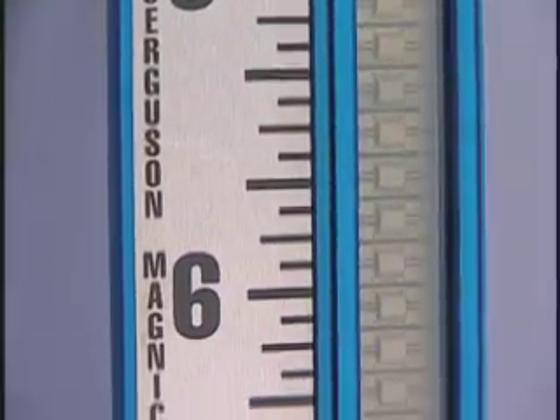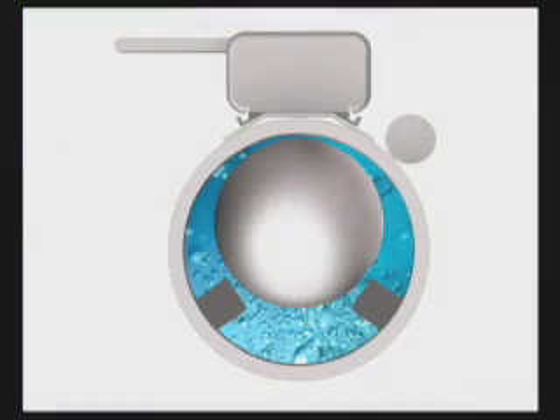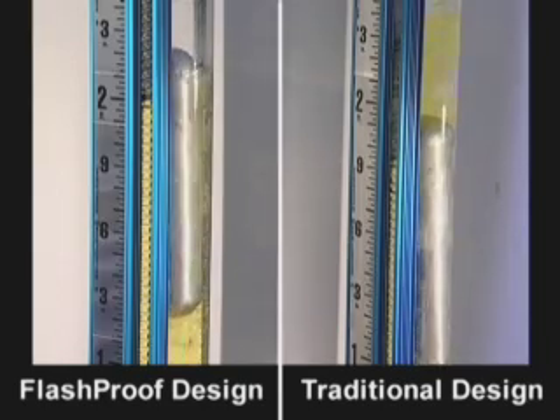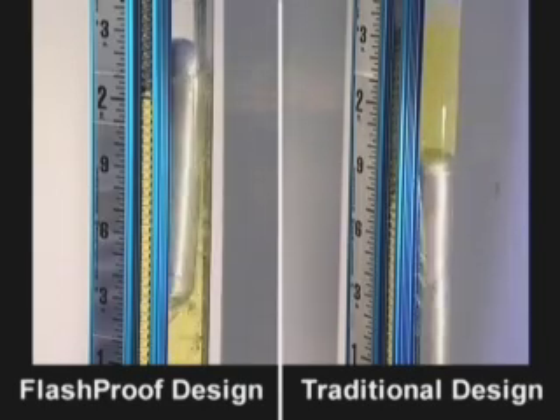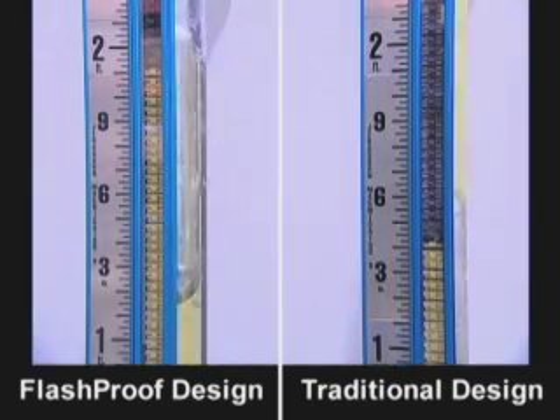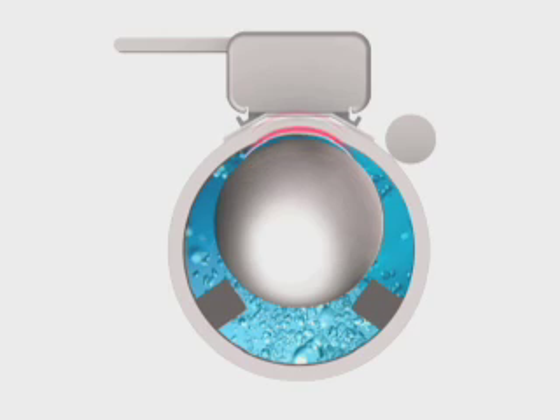The new Jerguson Magnicator Flash Proof Gauge features a unique chamber design to eliminate problems from boiling liquids and flashing vapors. By employing an oversized 3-inch Schedule 40 chamber with internal guide rods, entrained gases easily escape past the float. An accurate float level and indicator reading is maintained as the guide rods hold the float to one side of the chamber to ensure an optimized magnetic field in close proximity to the indicator, transmitter, or switches.